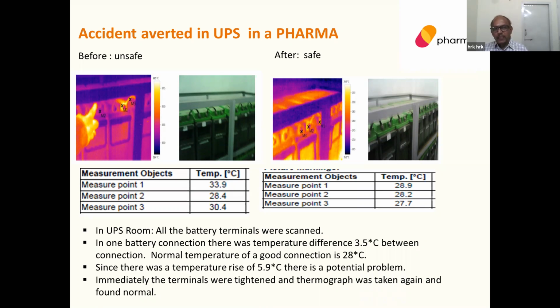In my experience, we went to a pharma unit and were taking thermography scans of the UPS system. As shown earlier, there was one battery terminal with a temperature rise of more than 4 degrees. Normally the batteries are kept at 25 degrees to increase the life of the battery. Otherwise the life will be drastically reduced.